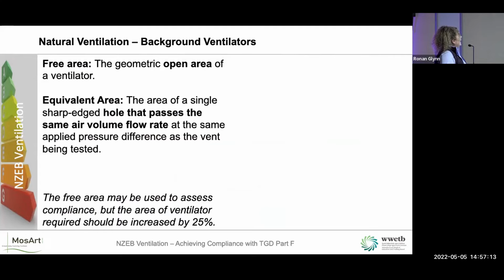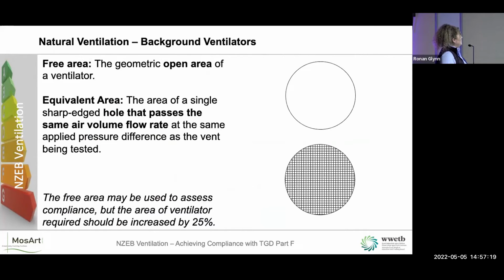So there's two ways of calculating the background ventilators. So you can have the free area, which is just the hole that's in the wall, or you can have the equivalent area. So obviously if we had just holes in walls, we'd have birds and insects and everything coming in. So we have a grill on the outside and a mesh on the inside. So the equivalent area has to be the area of a single sharp edged hole that passes the same air volume rate at the same applied pressure difference as the vent being tested, okay? That's really important. The free area can be used to assess compliance, but then you have to make the ventilator a quarter bigger. Okay, so that's worth noting as well.